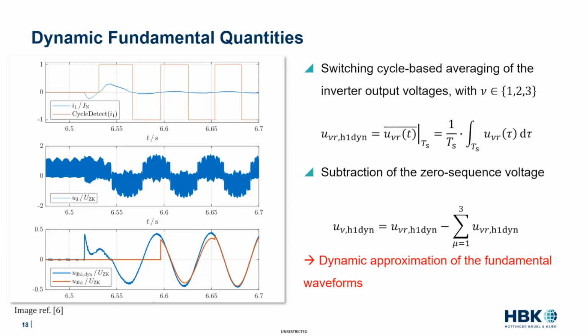Then you can see in the second plot one of the inverter output voltages, which of course contains the harmonic content of the switching frequency and looks like a, by principle, disturbed waveform with high frequency content. And if we now average this inverter output voltage with the dynamic method, based on the inverter switching cycle, you get as average this blue waveform.